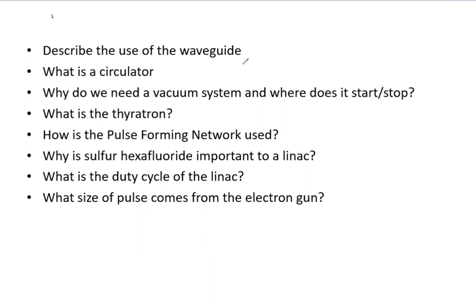So now circulator. In the waveguide, this circulator acts as a one-way sign essentially, where microwave power goes from the klystron to the accelerator tube but can't be reflected back to the klystron where it would cause some major damage.